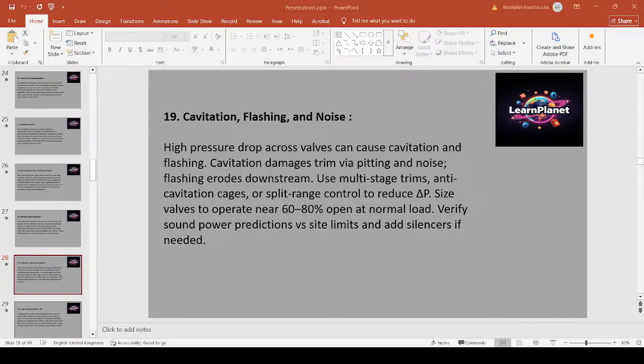Cavitation occurs when local pressure drops below vapor pressure and bubbles collapse violently, causing pitting and noise. Flashing is permanent vapor formation downstream. So flashing erodes the trim and downstream piping. Mitigate via staged pressure reduction, multi-stage trims, pressure recovery regions, or limit operating delta P via split range control. Valve sizing to operate near mid-stroke reduces trim wear and improves controllability. Acoustic silencers limit noise emissions. Example: on a high delta P boil-off control, replace a single-stage globe trim with a 3-stage cage trim and reevaluate sound levels.